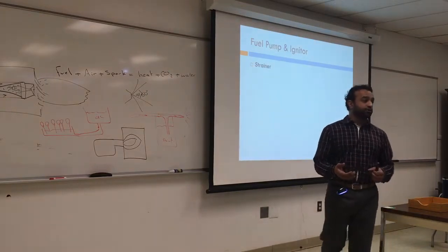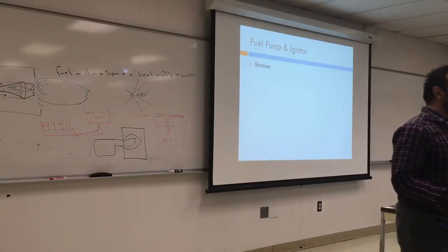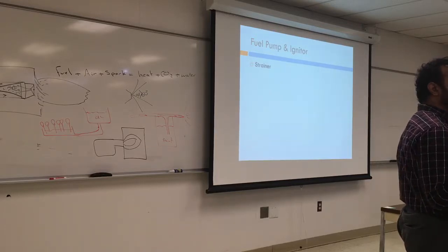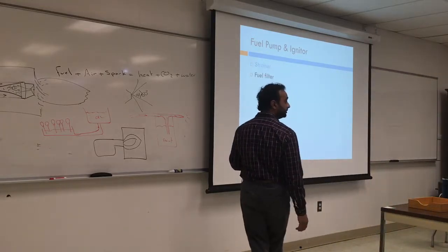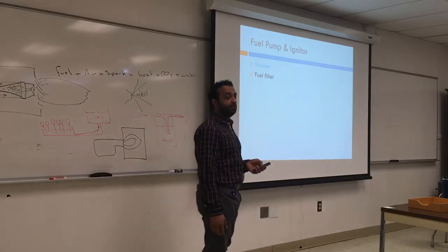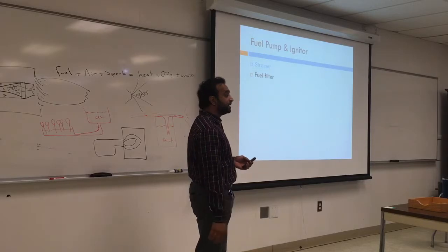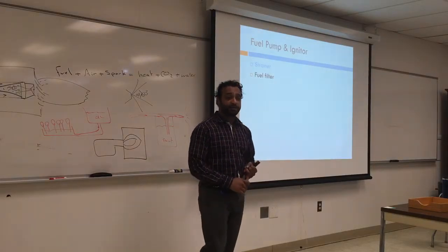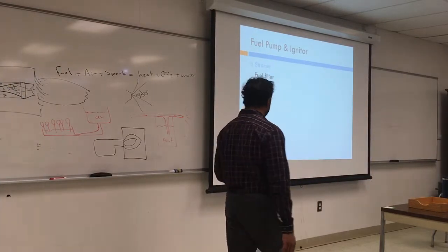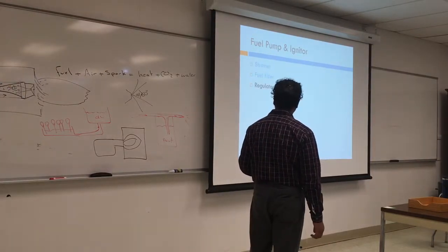The code now calls for an oil filter for most new pumps, so the oil filter should prevent the oil from having any contamination. And a lot of new pumps now are much cheaper and simply designed, so you don't take out the strainer, and you just depend on changing the filter. Fuel filter is a new practice again. Every boiler, every burner should have a fuel filter coming into it. And it will catch a lot of stuff: sludge, particles, chips from the tank, rust, and so on.